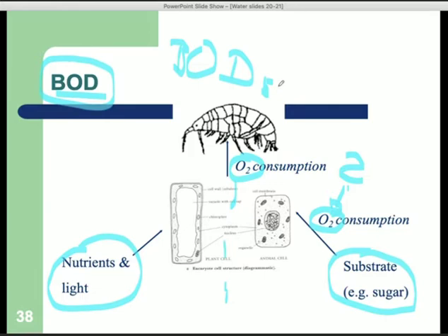And that then is the pretty much universal measure that environmental regulators use to control how dirty the water is. And it's also what operators need to know to identify how much oxygen they need to add to the plant. Because again, that's what a wastewater treatment plant does. It supplies this oxygen demand in the wastewater treatment plant bubble, so that we can then take that water, put it into the environment, and not have the environment experience this oxygen demand because the environment isn't able to satisfy that demand. I hope that makes sense.